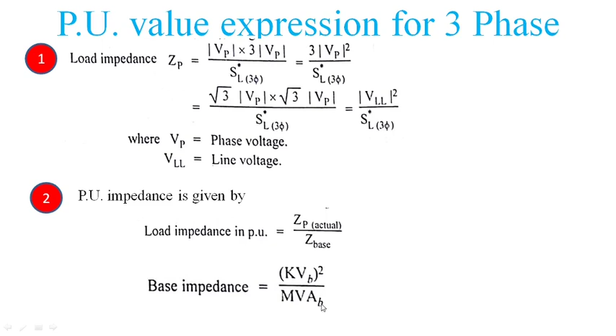Next, the per unit impedance is given by: load impedance in per unit equals actual value of load impedance divided by base value of load impedance, the same formula already seen. For a base value of impedance from kV and MVA, you can express it as a ratio of kVb squared and MVA-B, both being base values because we are calculating base impedance.